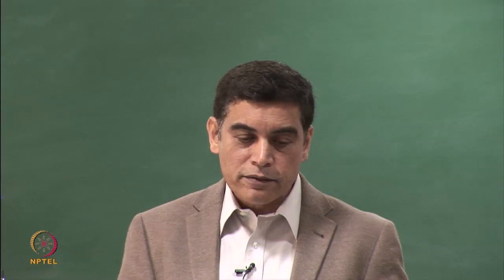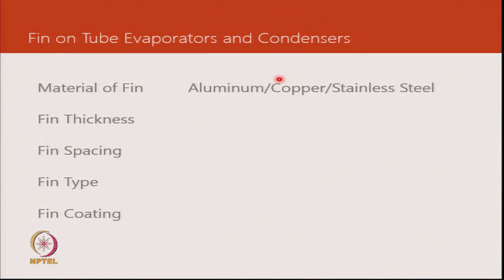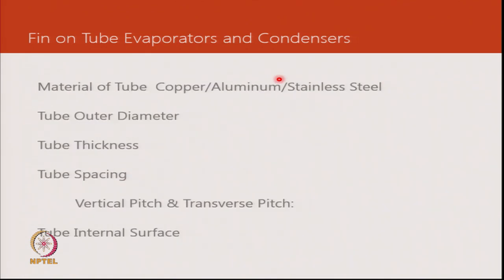So now if we look at everything that we have discussed about fin on tube design heat exchangers, then whether it is an evaporator or a condenser, we would need to define all of these. So we need to define the material, we need to define the fin thickness, spacing, and in a little while I will also take you through the coating part. So these are the parameters that are expected from an engineer when he is designing the evaporator or condenser. And then similarly on the tube side, what is the material of the tube, outer diameter, tube thickness, tube spacing, and when we say tube spacing, it is the vertical pitch as well as the transverse pitch, and the internal surface type.